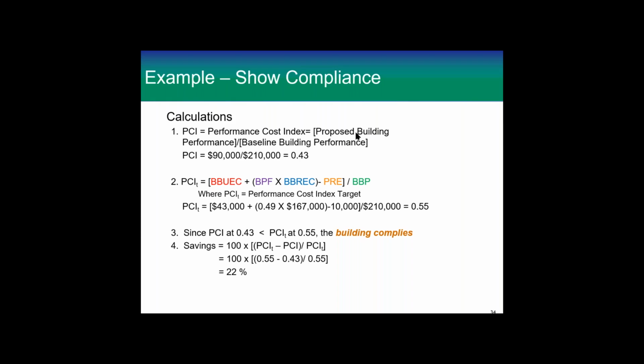Calculation is cost index equals proposed building divided by baseline building, which is the 90 divided by the 210, which is 0.43. And then you calculate your target, which includes that 0.49 as your baseline factor, and you come up with 0.55. And since 0.43, which is your actual, is less than 0.55, which is your target, then the building complies. And you can go back and plug it into that first equation on that first slide, and you can see that you've actually saved 22% more than a building that just complies. And that's the way it works using this new way to use Appendix G since 2016.